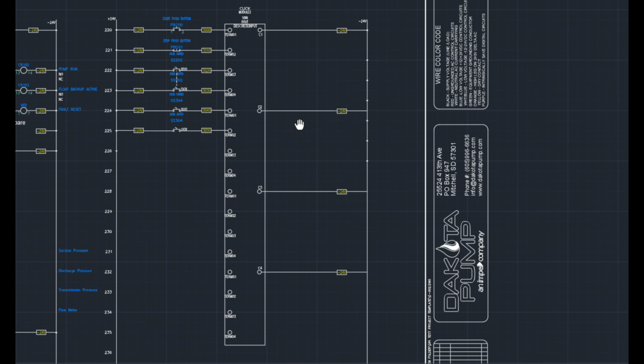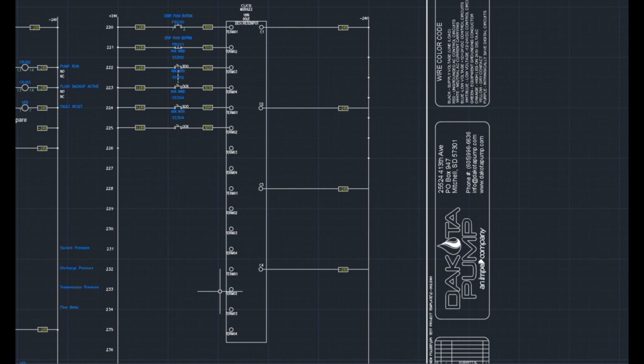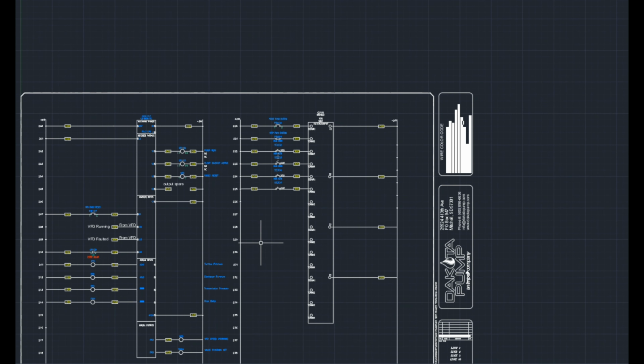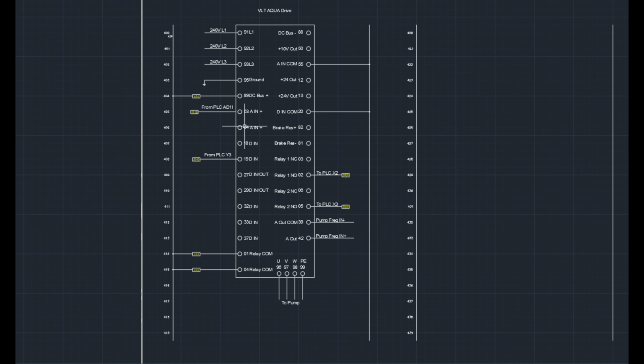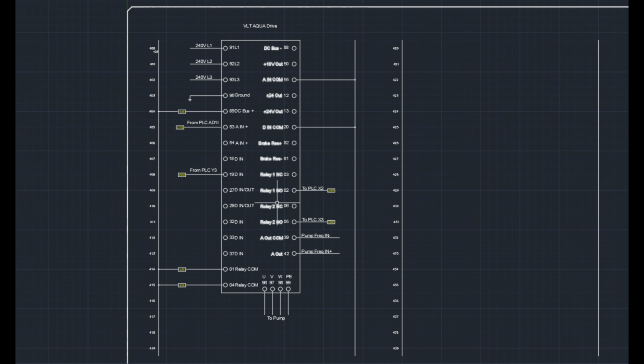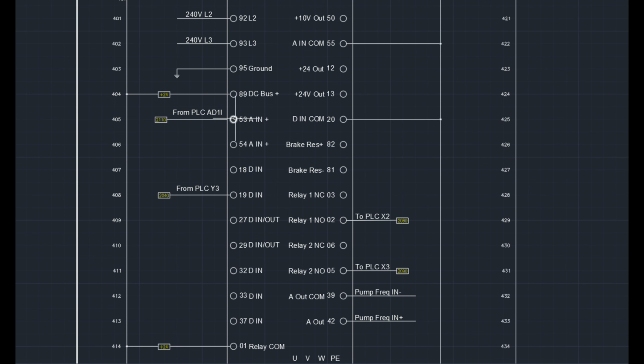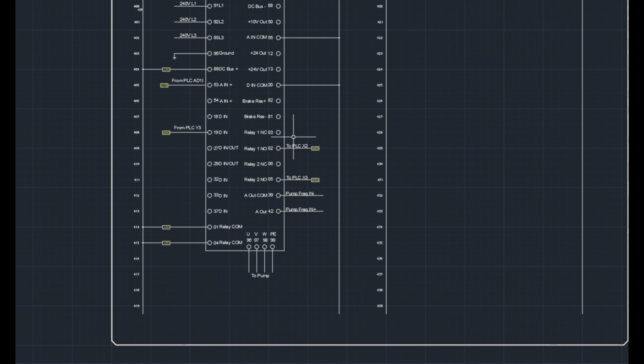The 16 digital input module was moved here because everything else freed up a whole lot of space. So these are the only 2 modules I'm actually using in the panel. And if we move on here, we can see my VFD wiring. And the only thing that has changed here is, like I said, the 53 port for the analog input for the VFD so that we could send the frequency to the VFD to get to the pump.